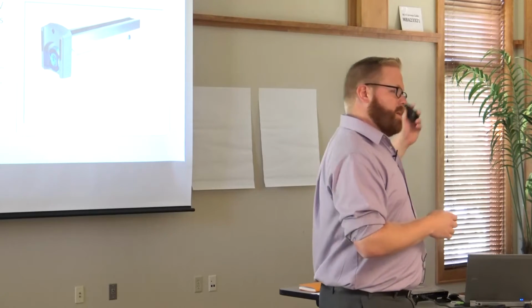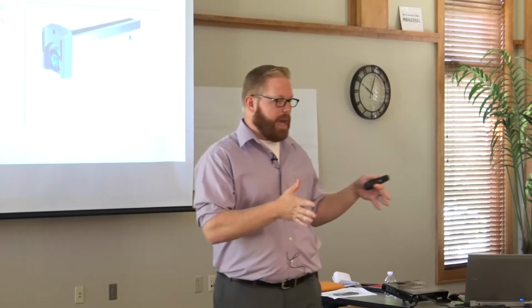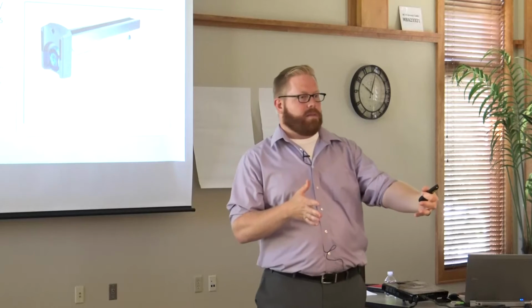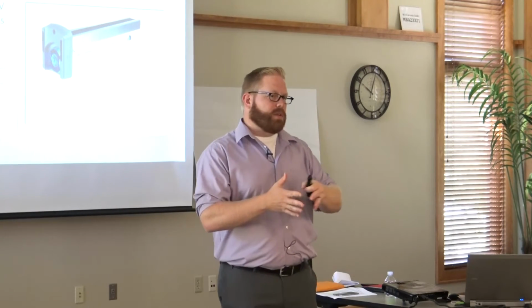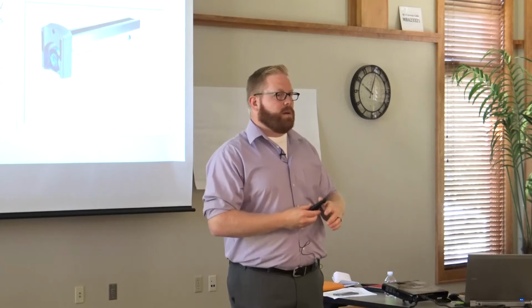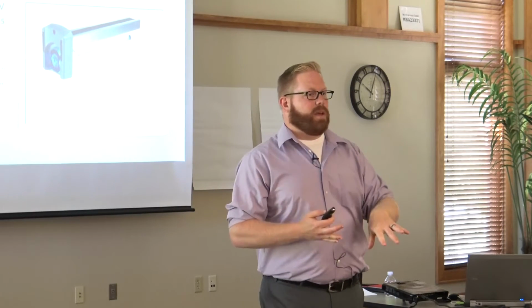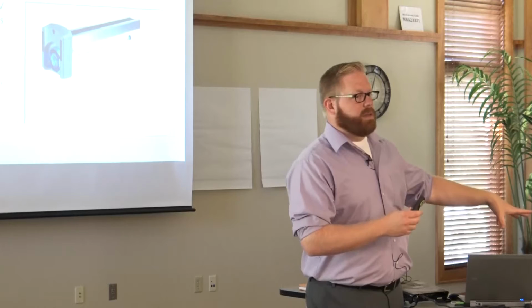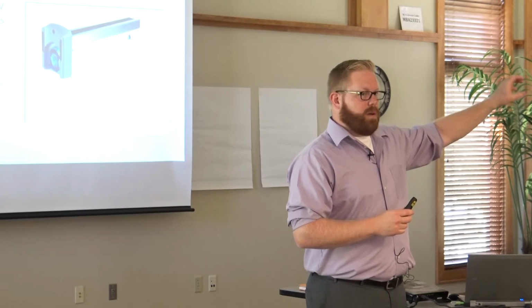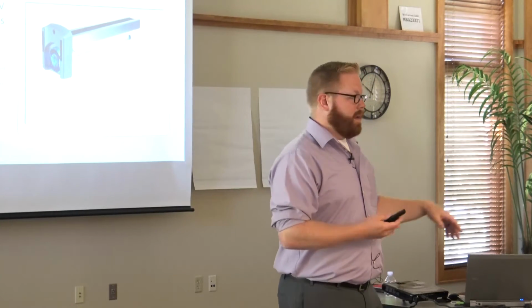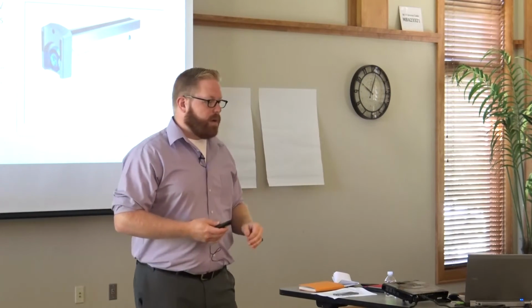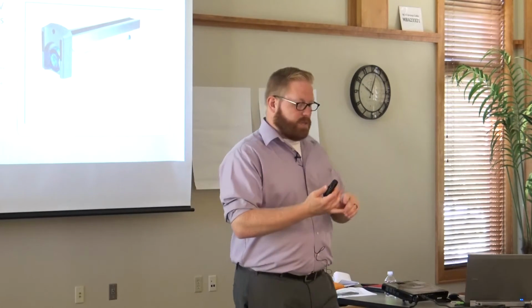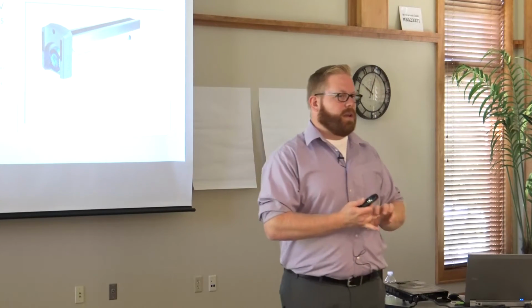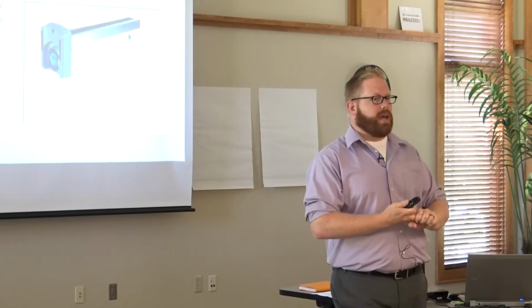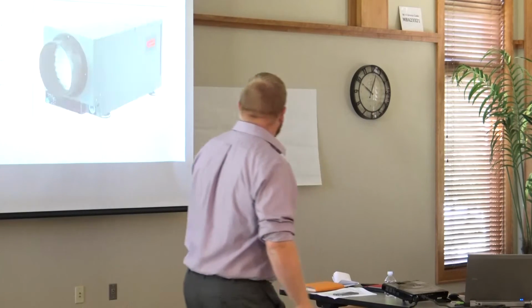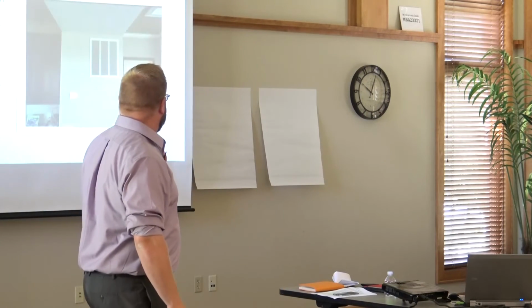It's important to know some of this stuff on the front end to ensure the end product, the house you're selling, has a good performing system. Doing that Manual J or upfront calculation at least makes sure your equipment is sized right. But then it's the ductwork, making sure that's sized right. What I feel is most important is the commissioning, because you need to check combustion, check your airflows, check your static pressures. I'll get to a slide that shows some of that.